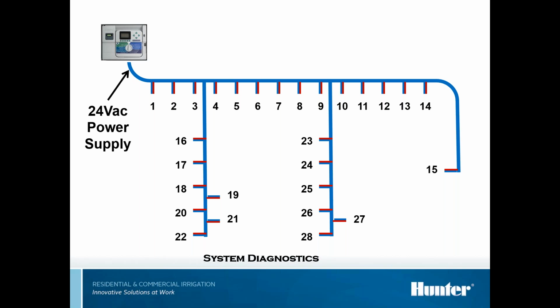Now, if you hook up your 24-volt power supply and suddenly you get a high number, 2318 in this instance, you can go out there and start either breaking it and see if it goes down to a normal number, or you can use your clamp-on meter and start looking. So at that point, between 9 and 10, if you have 47 going out, okay, well, that one's fine. That's not a problem. If you look at that number, you have 2,224 milliamps. Okay, so your problem is going to be after that point.